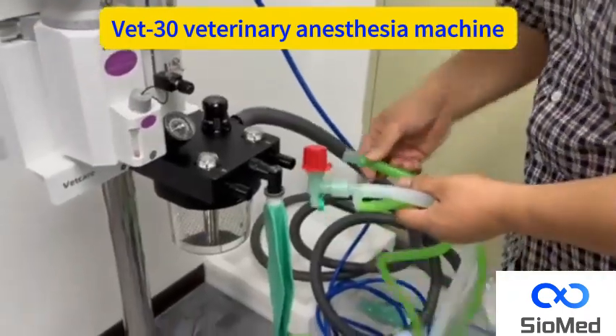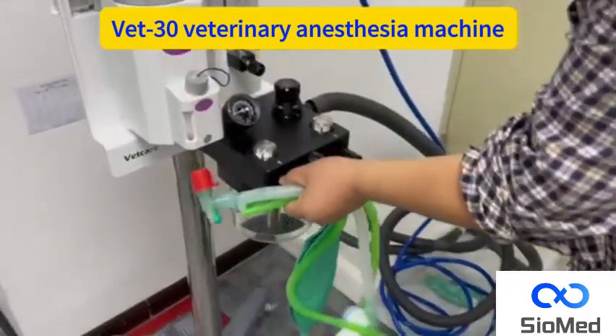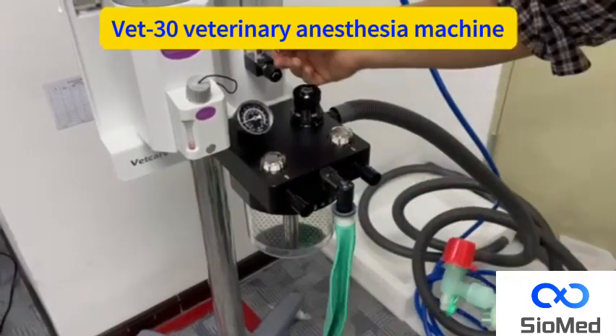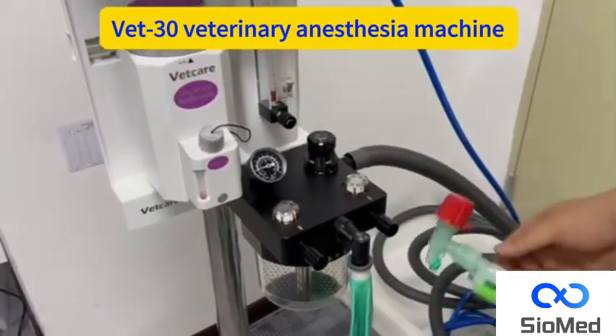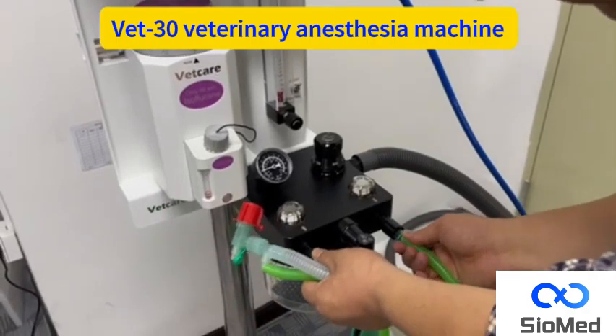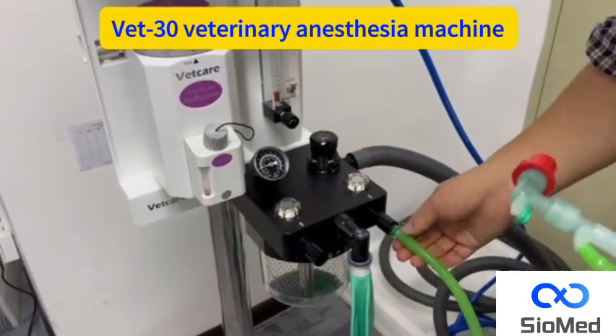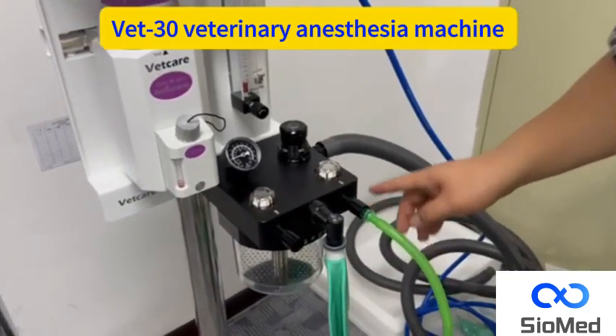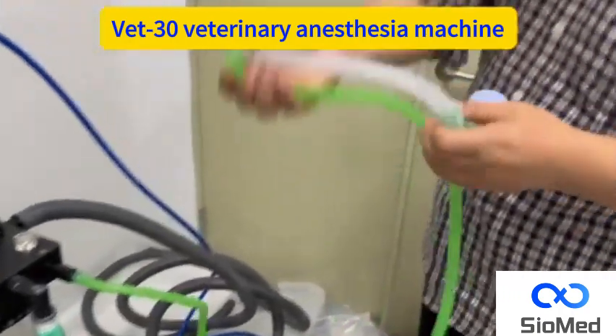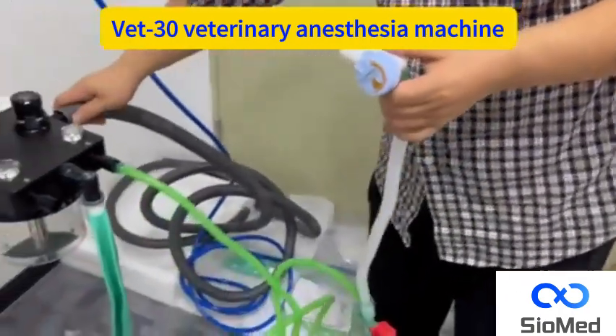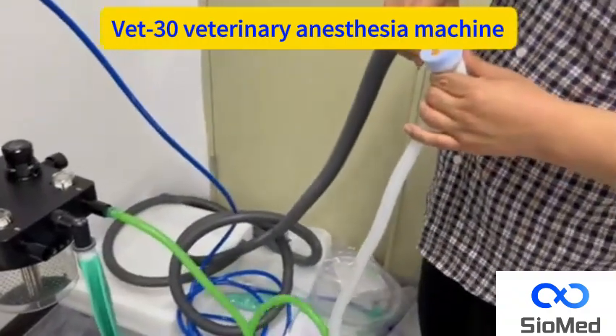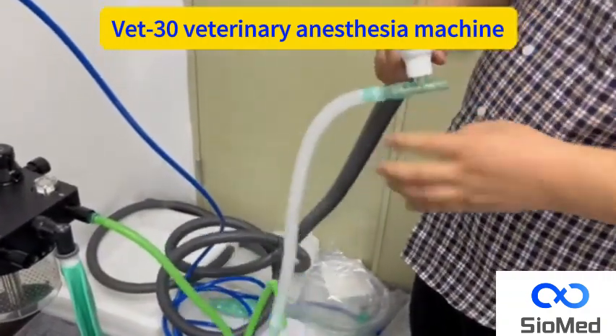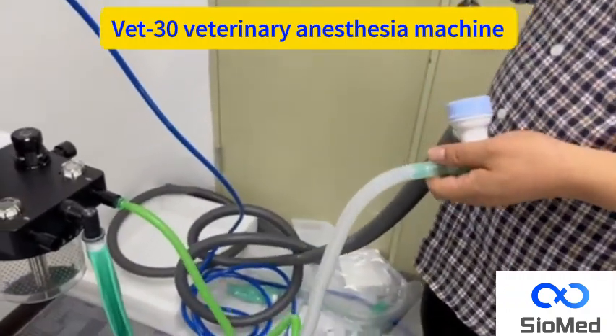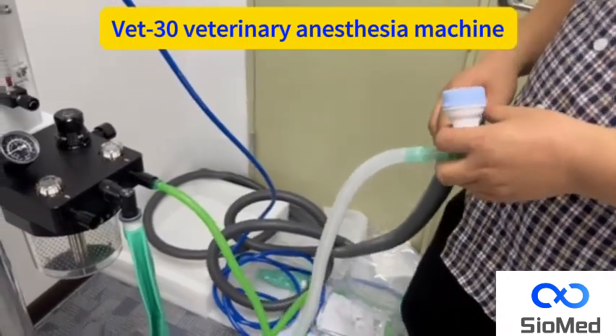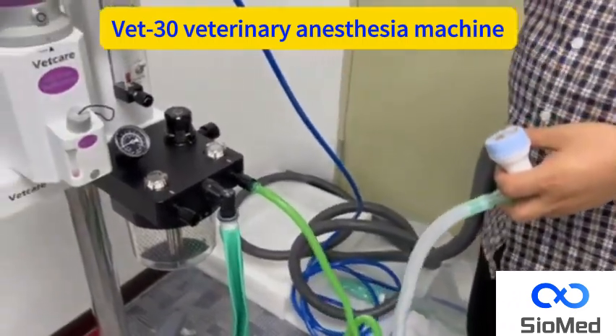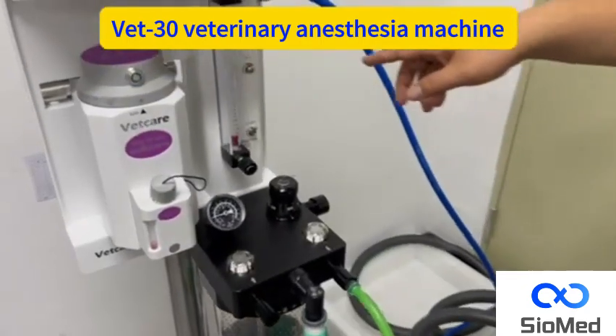If the small animal anesthesia requires a non-rebreathing circuit, we adjust the toggle to ACGO mode and connect the T-piece tube to the suction interface. At this time, the exhaust pipe is connected to the APL valve at the other end of the T-piece pipe. Finally, we will briefly introduce the functions of the Vet30 anesthesia machine.